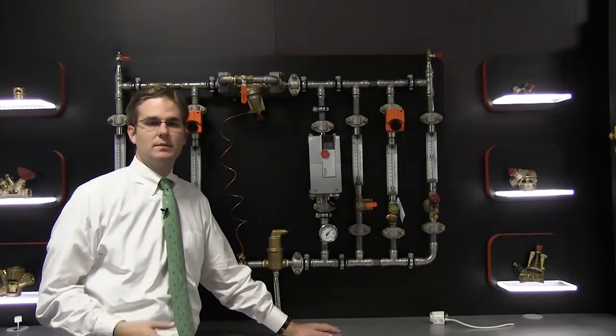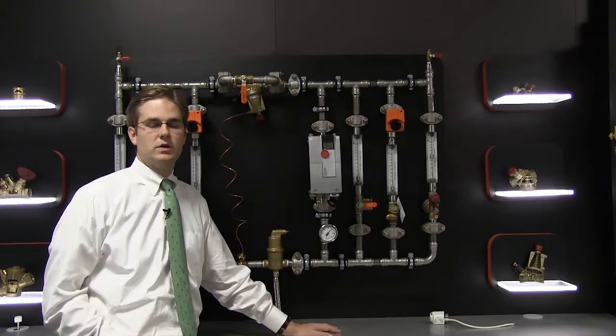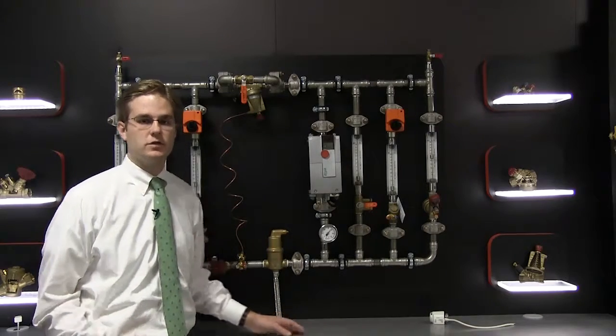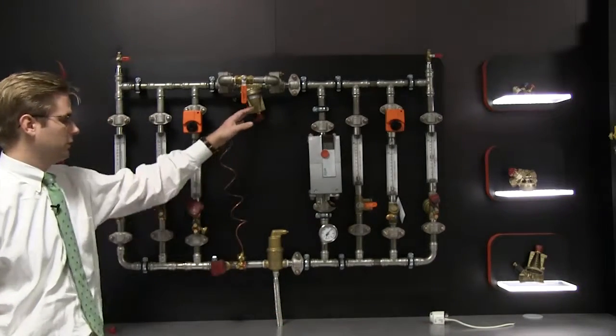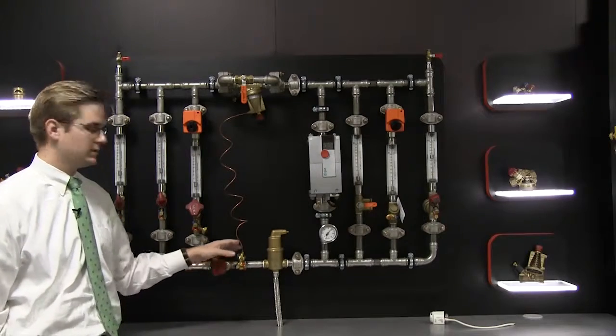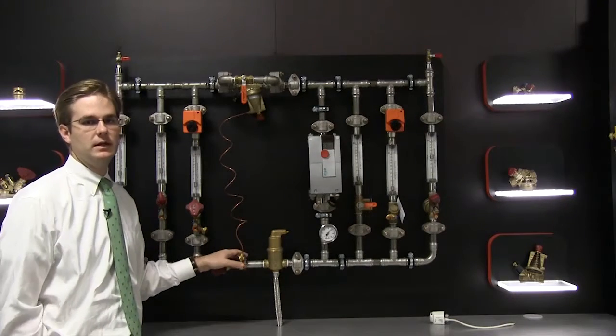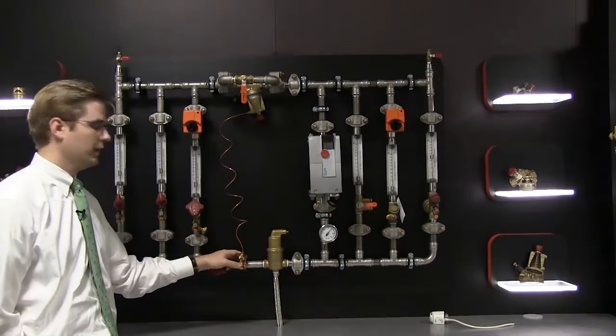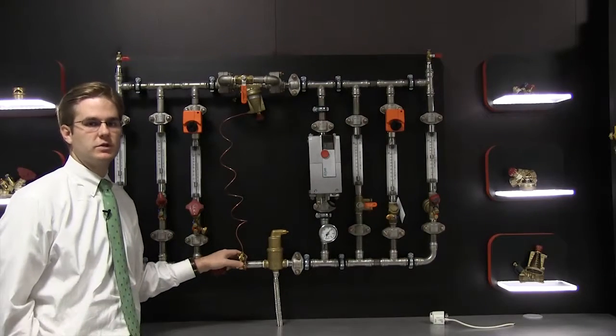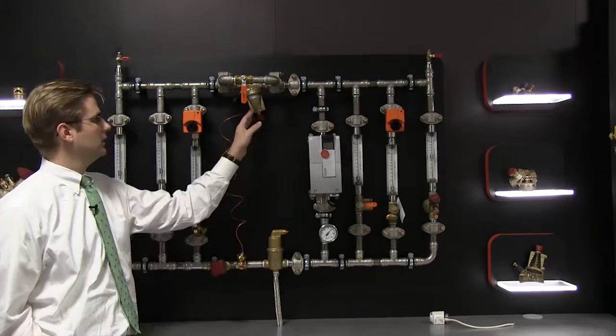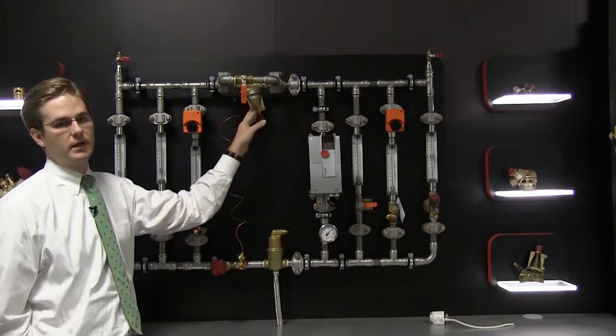Pressure-independent balancing means maintaining a designed flow rate at each terminal at all times. The first way that we do that is by using a differential pressure control valve. What this does is it takes a pressure signal from the inlet of the branch, and if there's a pressure spike, it closes down, and if there's a pressure decrease, it opens up.